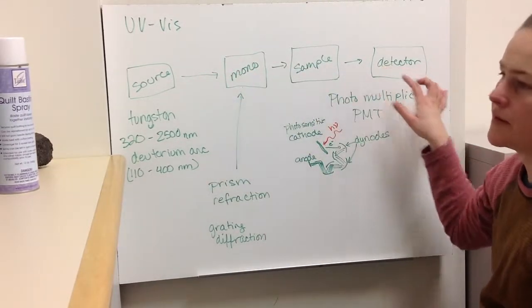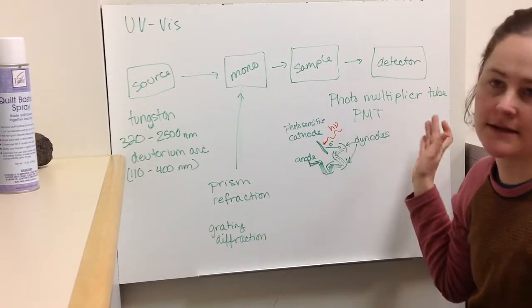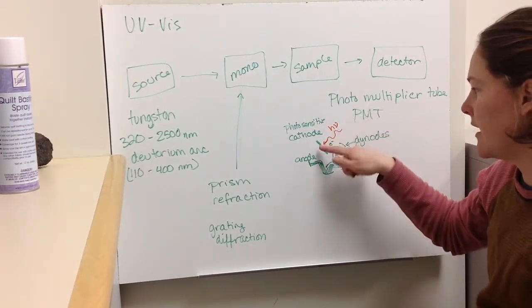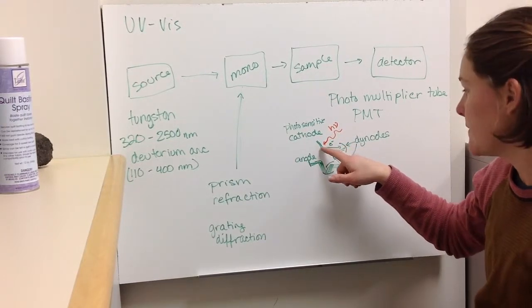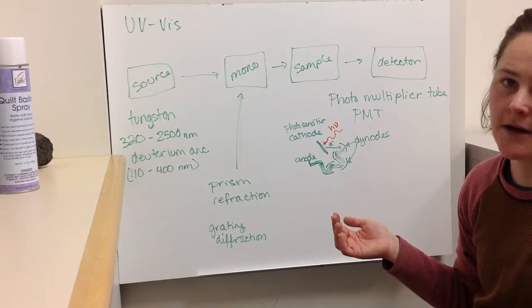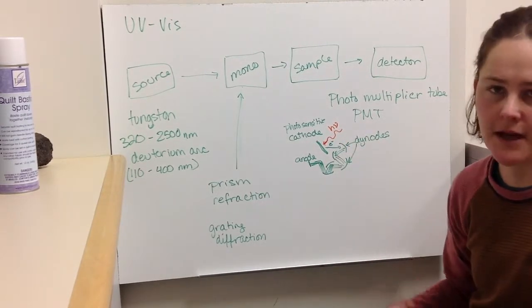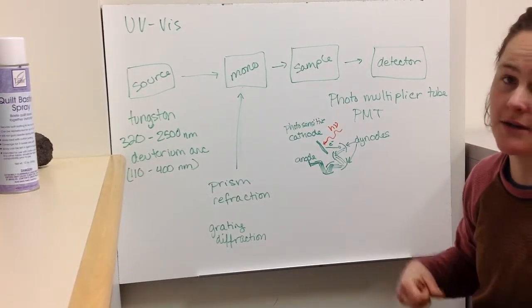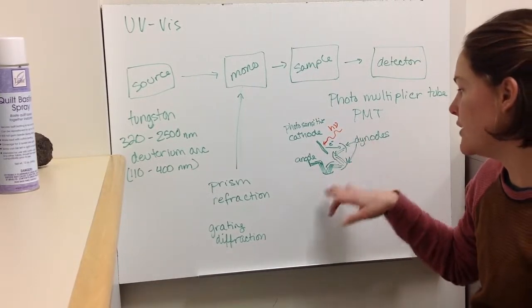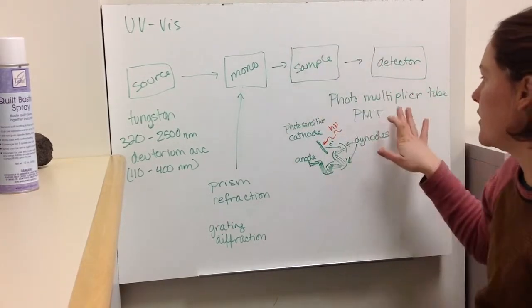And so with this sort of setup, you're going to probably be doing a single wavelength at a time as you scan your monochromator. So you only need to detect one wavelength at a time, so you're going to use a photomultiplier tube, where you have a photosensitive cathode where the light photons come in and hit it, that generates electrons, and then you have a series of dynodes that multiply that electron because they're at progressively higher voltages. So you start with maybe 90 volts, and then 180, and it's a difference of 90 volts every time. So those electrons, one hits, and it's a cascade effect, like three more rush on to the next dynode. And then eventually you get over to the anode, and you can get a 10 to the 6 amplification using this method. So that's called a photomultiplier tube.